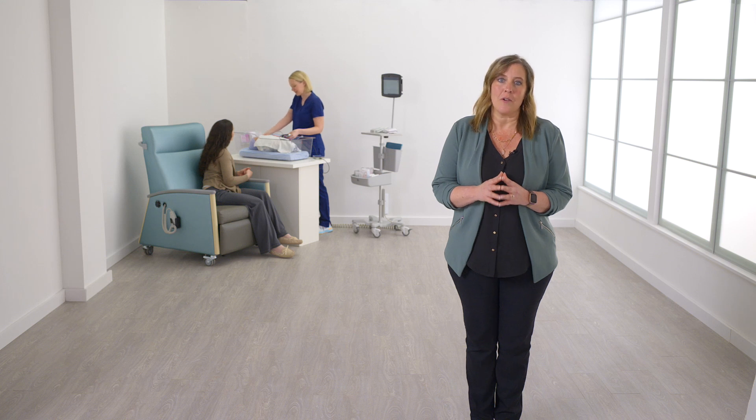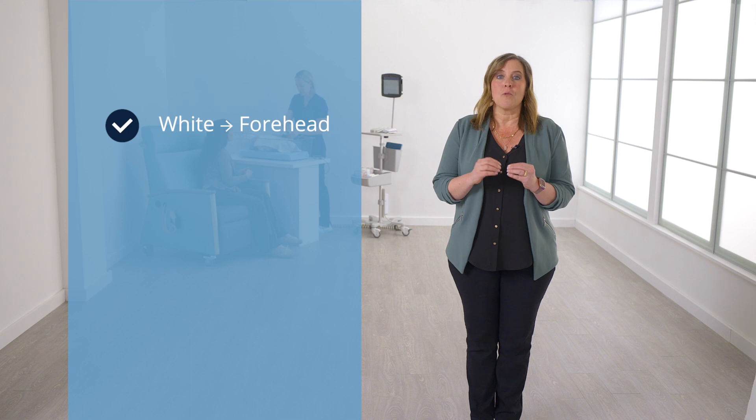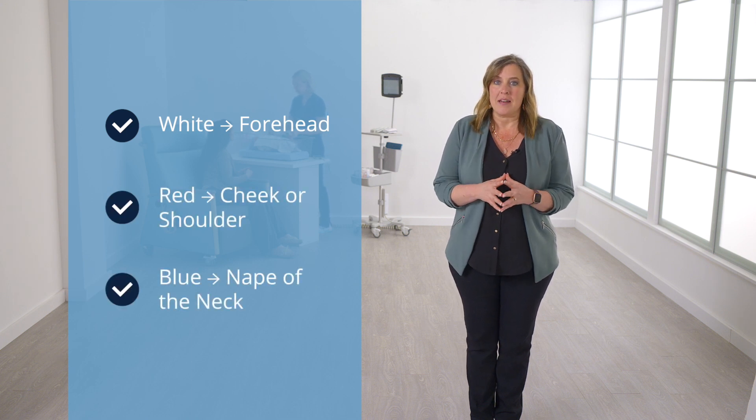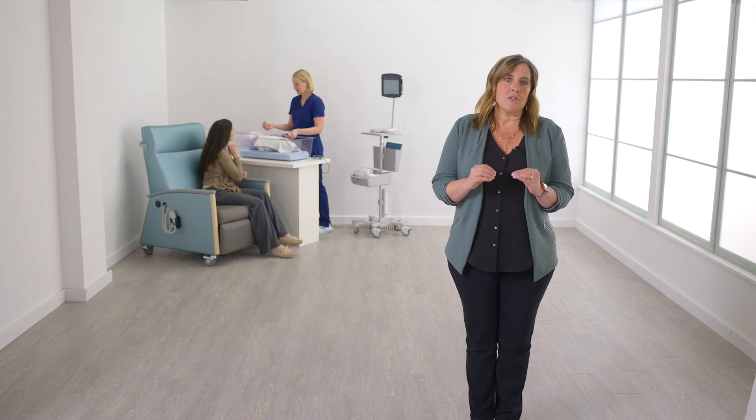patient's head in very specific locations. The white electrode should be placed on the forehead, the red electrode on the cheek or shoulder, and the blue electrode on the nape of the neck.